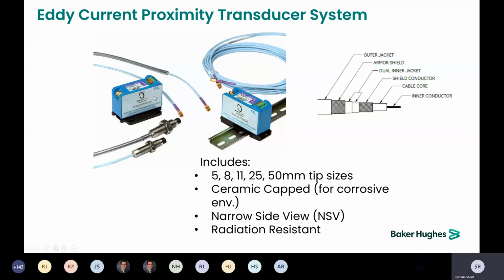So here, again, I mentioned at the first that we had the blue bits. Here we've got the purple bits. So this is a different setup. And so I believe this is either the 11 or 25 millimeter. I can't remember what purple is. So proximeter, probe, and cable would all need to match. We offer a 5 millimeter, 8 millimeter, 11 millimeter, 25 millimeter, and 50 millimeter tip sizes.